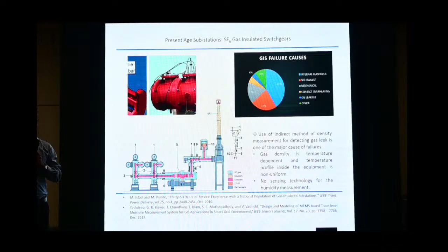So if you can manage that, the first advantage you get is that you can miniaturize the size of the device. Getting my point? You will get the same standard voltage rating, same current rating, same power rating, the desired one, as compared to an open substation, but with a miniaturized size, with all equipment installed inside. Understand? Why do you need it?